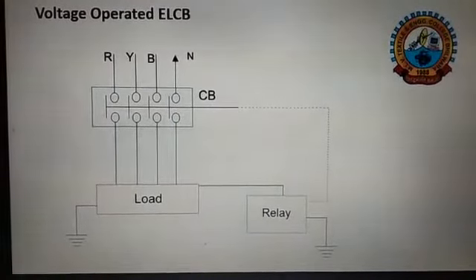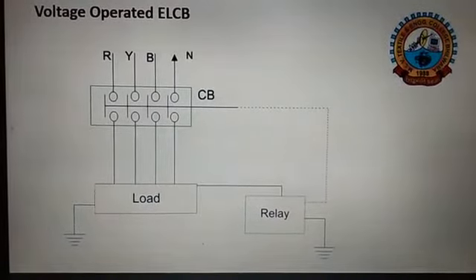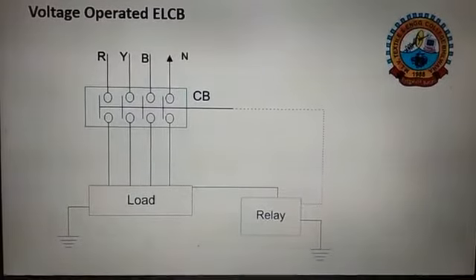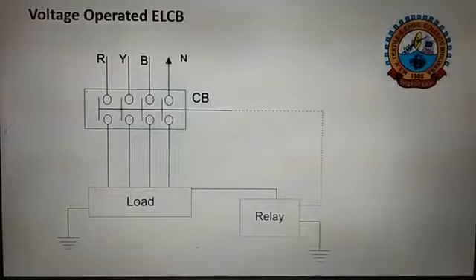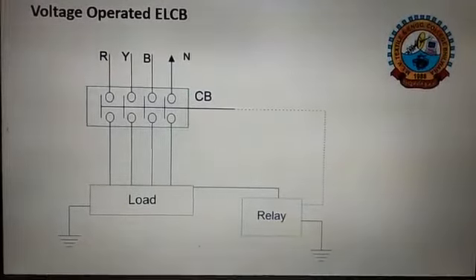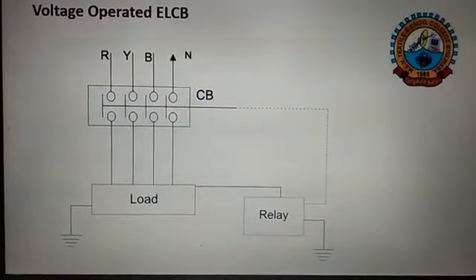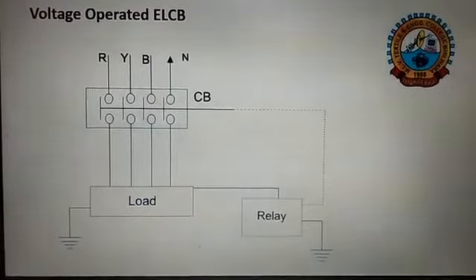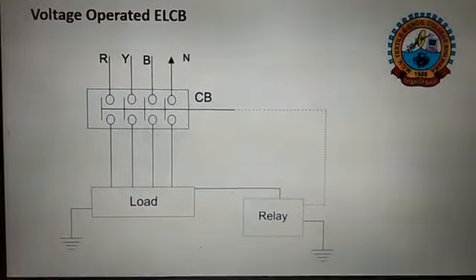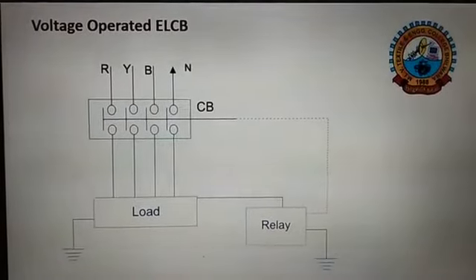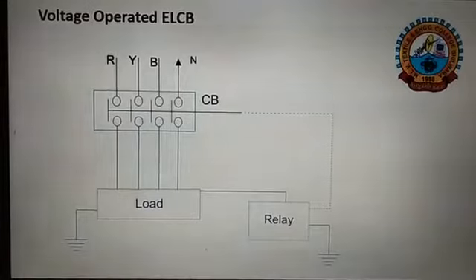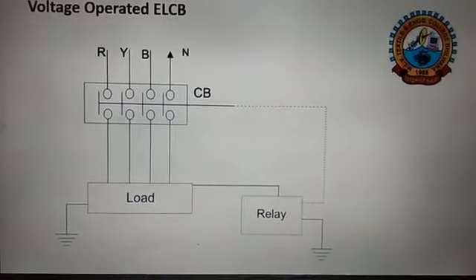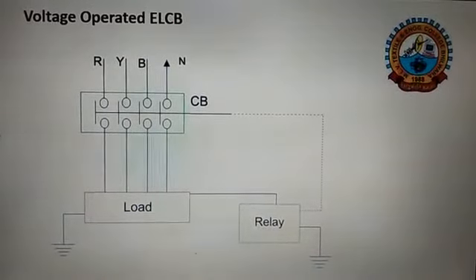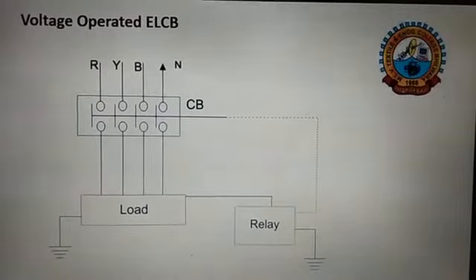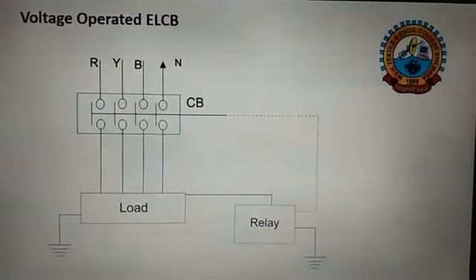Continuously it will check the potential difference between the earthing and the positive points, or you can say the line supply. In this example I have taken 3-phase star type equipment. There are 3 phases R, Y, B and 1 neutral point. So it will continuously check the difference between R to the earthing, Y to the earthing, B to the earthing, as well as neutral to the earthing.